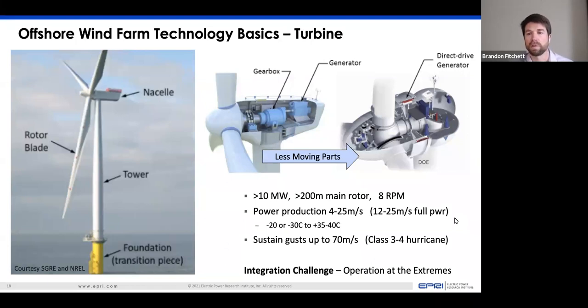Of course, these machines are getting much larger, more than 10 megawatts, more than 200 meter main rotor sizes we're talking about. But the power production regime has not changed much in the last 40 years. Power production is typically somewhere in the range of 3 or 4 to 25 meters per second. I've seen that recently start to get expanded in some of the newest wind turbine models out to 30 meters per second, with some reduction in power output to reduce the mechanical loads.